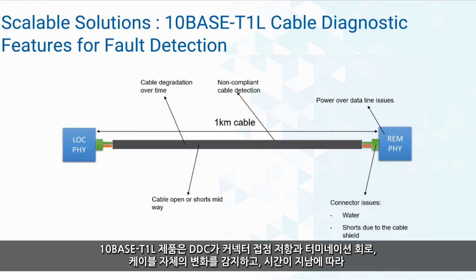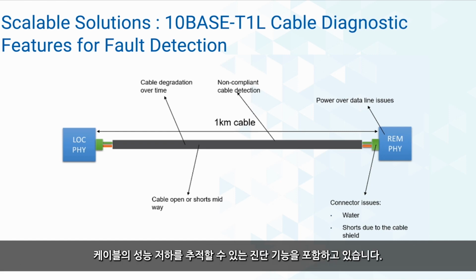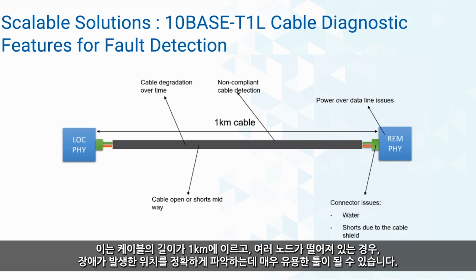10BASE-T1L products have diagnostic features that enable the DDC to detect changes on the connector contact resistance, the termination circuitry, the cable itself, and even track cable degradation over time. When you have a cable with a possible length of 1 kilometer and multiple nodes apart, this can be a very handy tool to pinpoint where the fault has occurred.